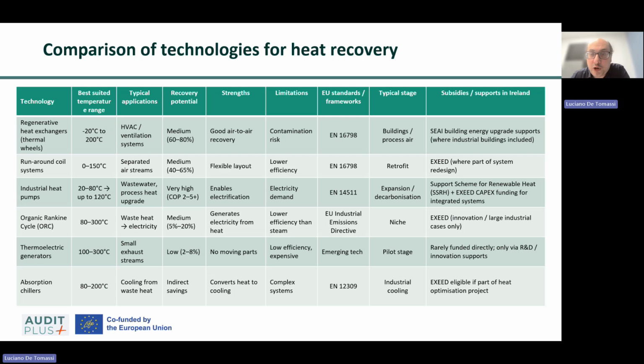Absorption chillers use waste heat to produce cooling rather than directly recovering heat for heating purposes. They typically require heat sources between 80 Celsius degrees and 200 Celsius degrees or higher, and are widely used in hospitals, district cooling systems, industrial facilities, data centers, and large commercial buildings. Their coefficient of performance generally ranges from 0.6 to 1.3.